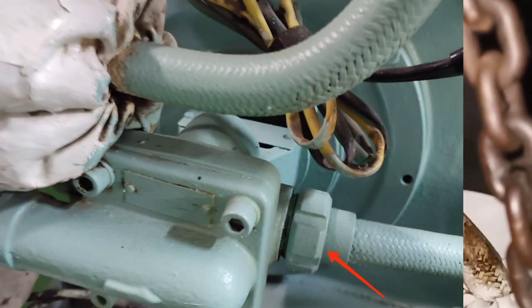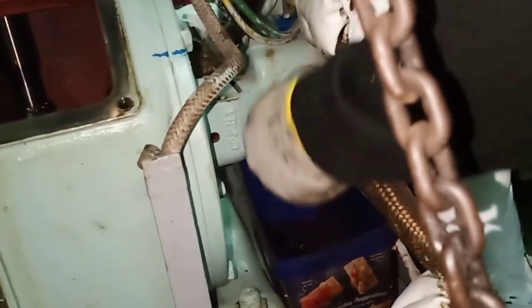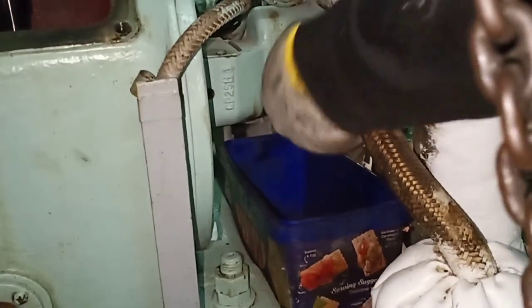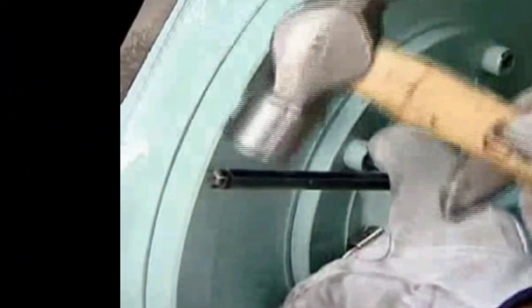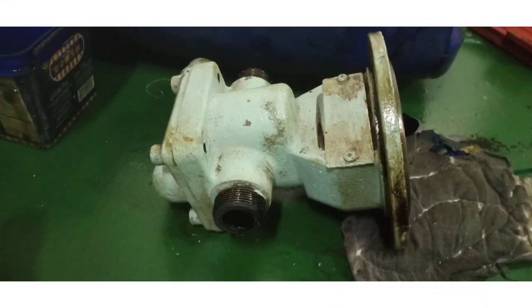Remove the cup nuts of the connecting tubes at the gear pump. Make sure to place a container under the pump to receive the oil that is drained off. Remove the bolts tightening the gear pump with the hexagon rod spanner and remove the pump from the main body.